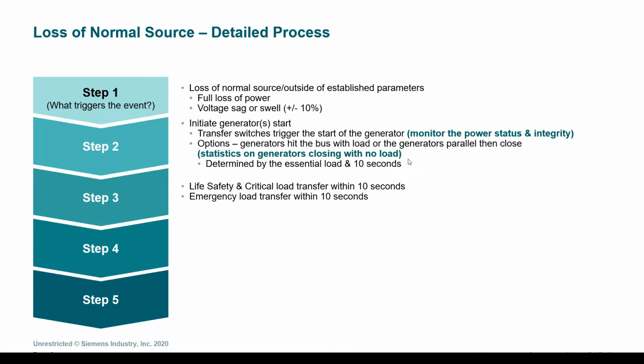Step 3, the life safety and critical load transfers over within 10 seconds, or in a non-healthcare facility, the emergency load would transfer over within 10 seconds. Moving on to step 4, the equipment transfers in stages, and this can be determined by priority of the equipment that they want to see on that, and we'll talk about that in a little more detail in a little bit. And lastly, the optional standby transfers in stages, again, based upon priority and availability of generator power.